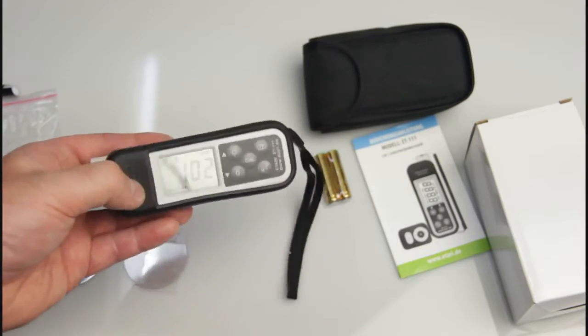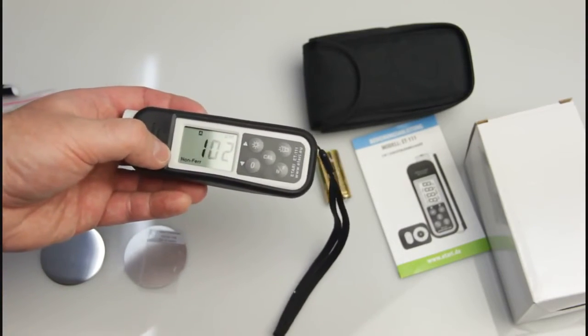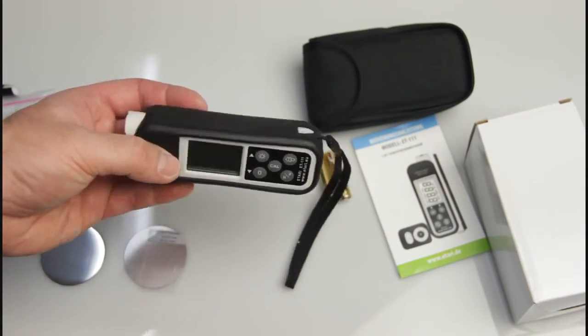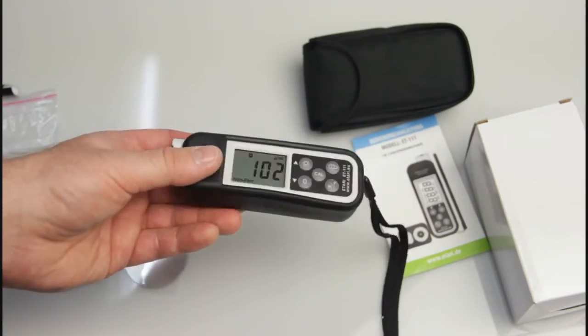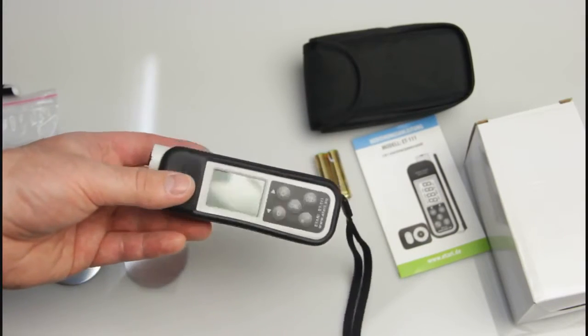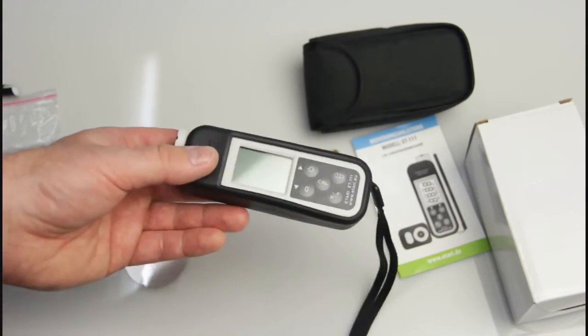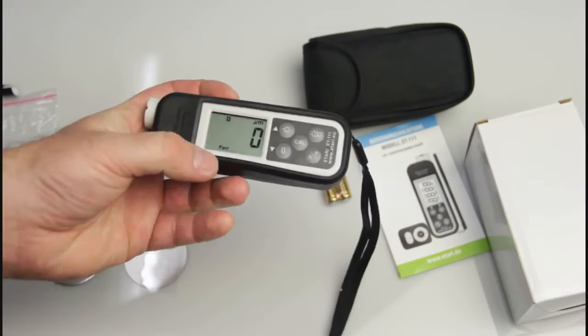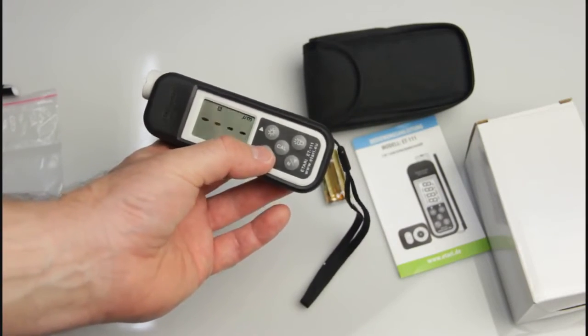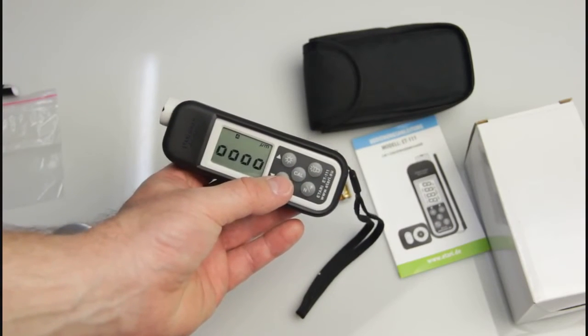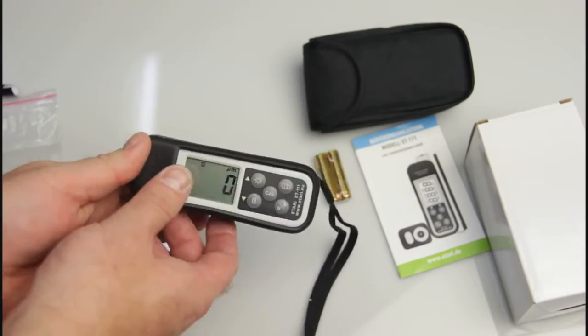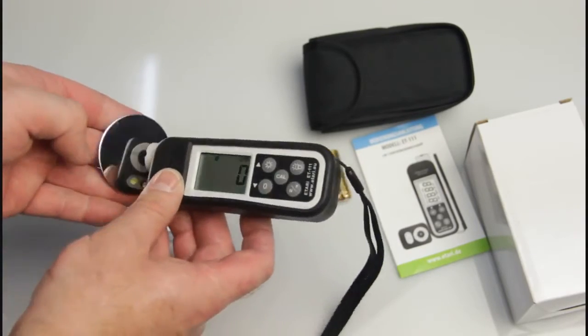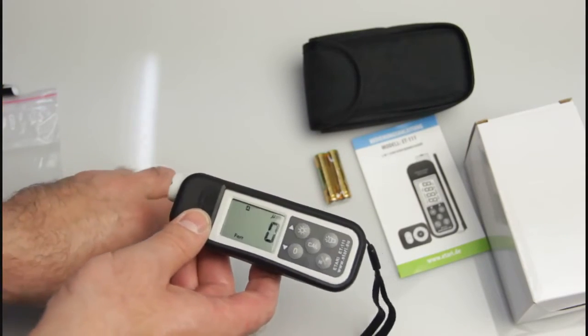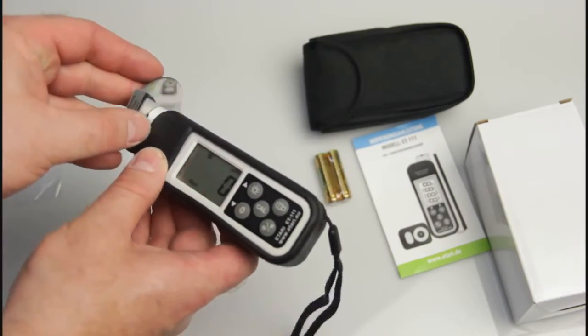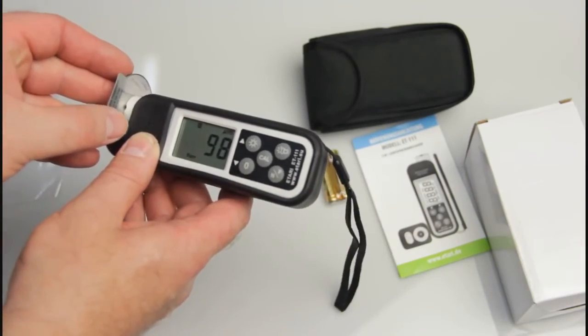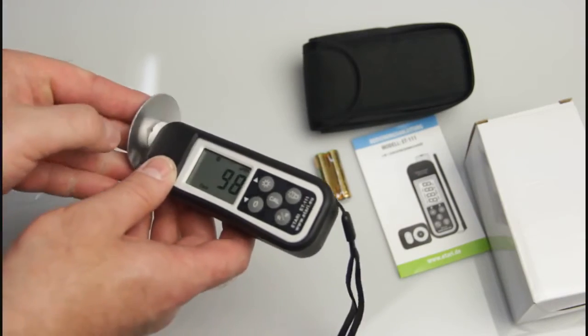Well, one more interesting feature in this gauge is resetting. Let's say something happened with the gauge, you see that it goes crazy. Sometimes it happens with all electronic stuff, and you can just reset to the factory default. How to do it? You just press the 0 button for 4 seconds, and here it is. It's in the factory default settings, and while you do it, you get an almost calibrated device.